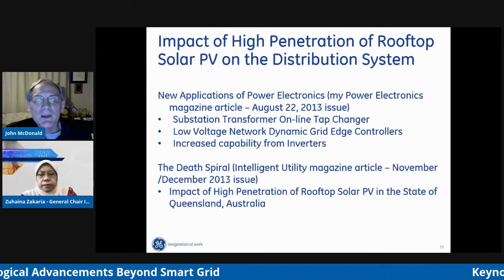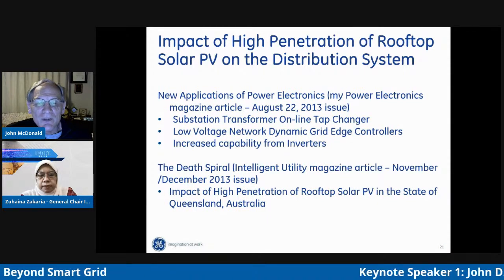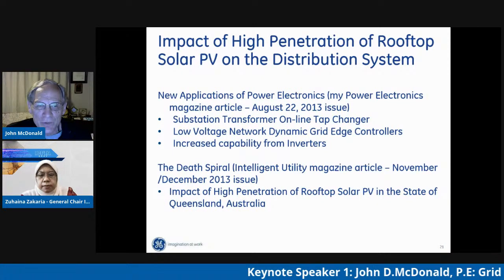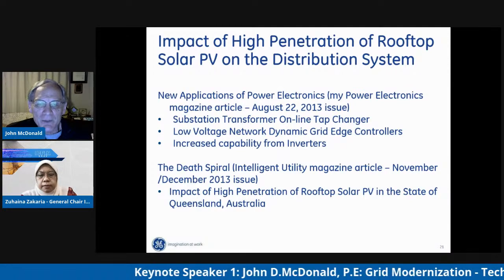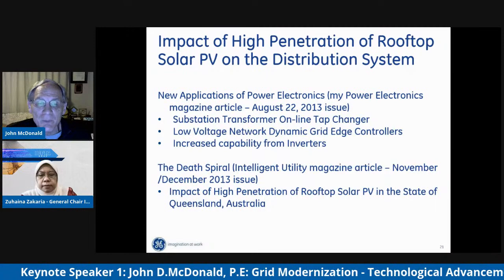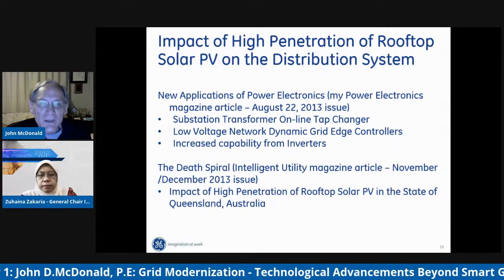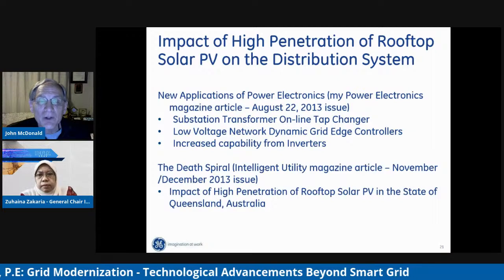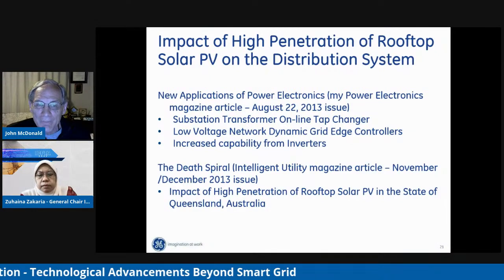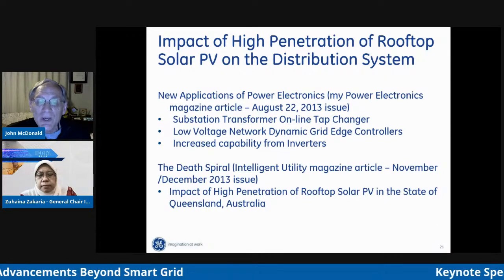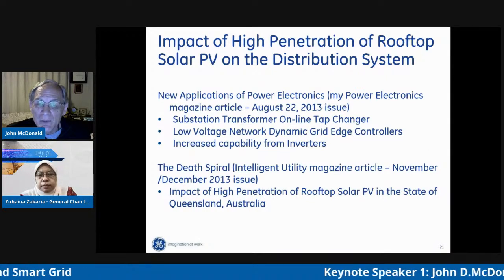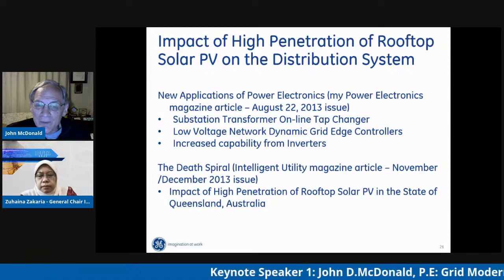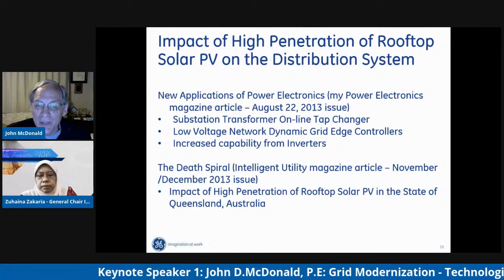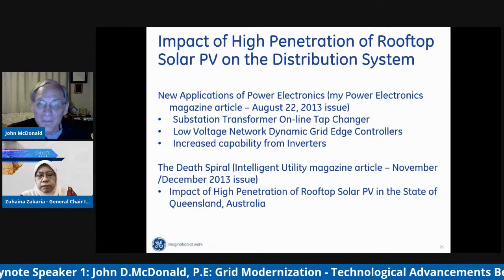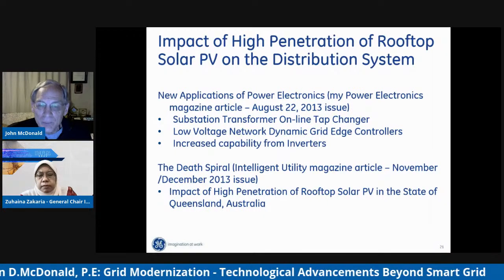So the continuing use of mechanical controllers on the grid as the penetration of renewables grows is just not feasible. That's why we and others have built prototypes of a power electronic based tap changer, and that's why we have these grid edge controllers—that's why we're talking about much smarter inverters with not only increased functionality, but greater external control capability. This is real, and as the penetration of renewables grows, we're going to see this more and more often.